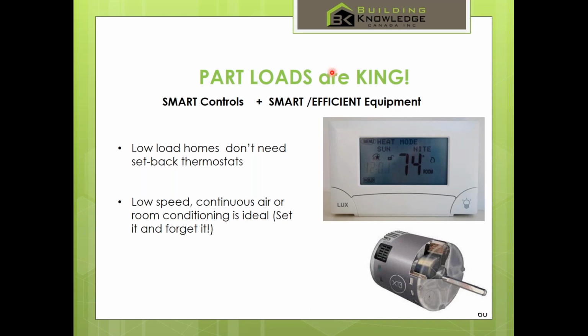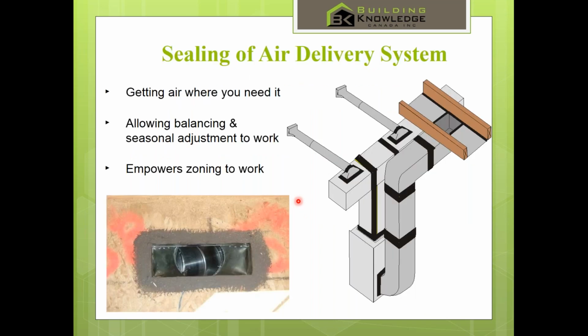A couple additional items. Part loads are king. Low load houses, Code Built, Energy Star, Net Zero, R2000, are all low load houses. These homes will likely never operate at high load unless the Joneses open all their windows in the second week of February and have a party. These low load homes do not need setback thermostats, because the setback thermostats simply do not work, but they need smart thermostats. They need low speed continuous air or room conditioning as an ideal. So set it, forget it.